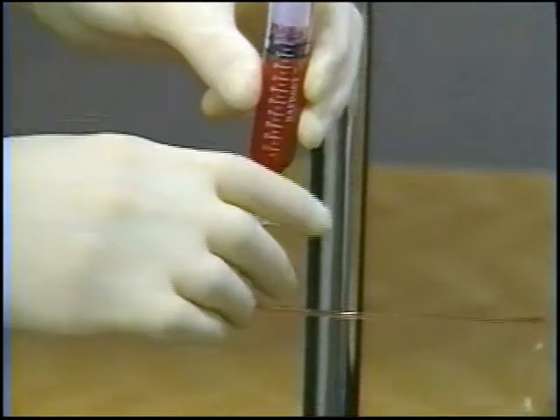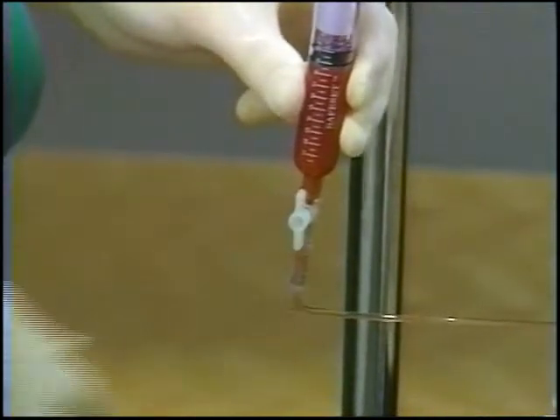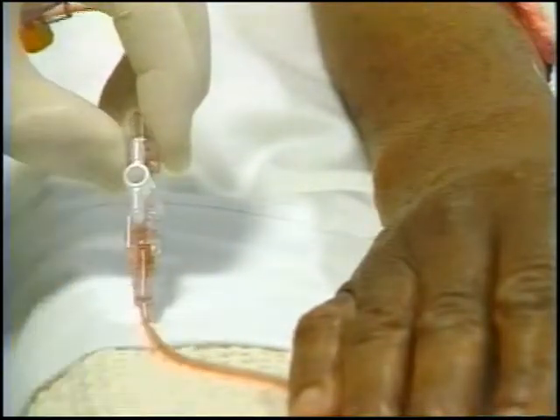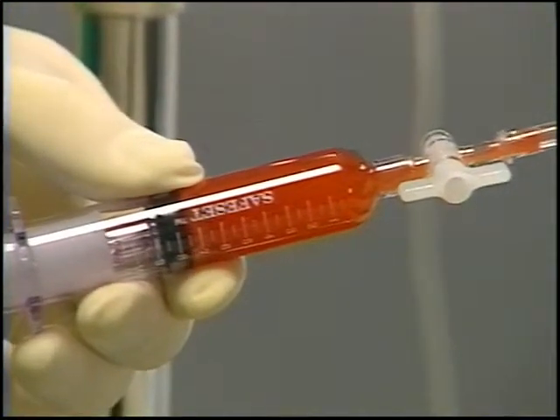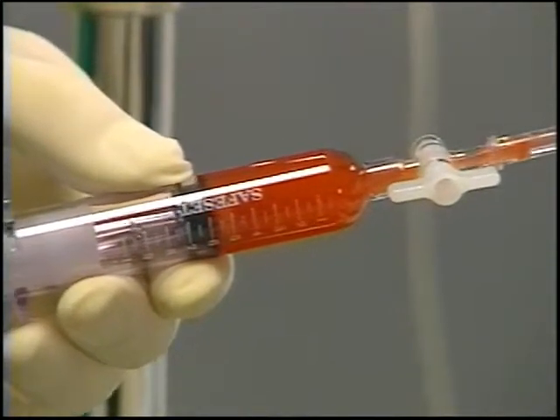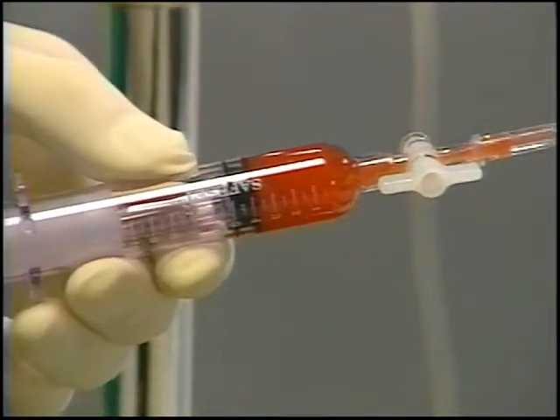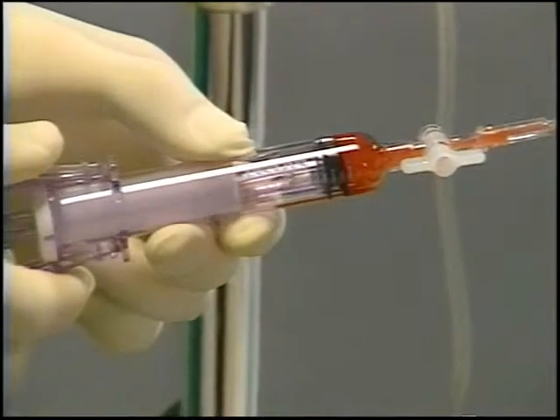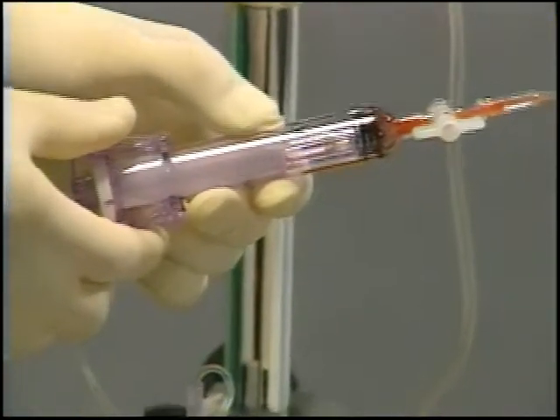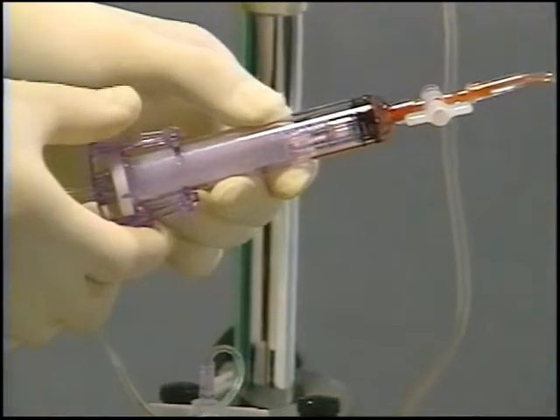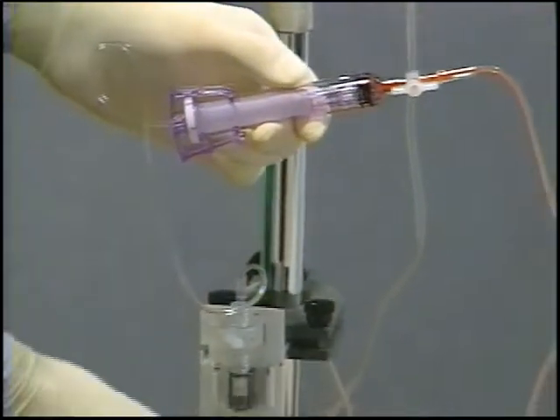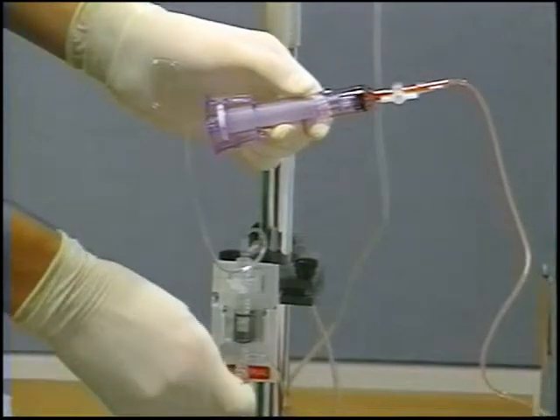Then, turn both the one-way stopcock at the tip of the reservoir and the one-way stopcock near the patient back to the on position. Finally, return the reserve fluid from the inline reservoir to the patient by slowly pressing down on the plunger. Return about 1 cc per second until the plunger reaches its locked position. Once the Safeset inline reservoir is in the locked position, activate the flush device until the line is clear of all blood.